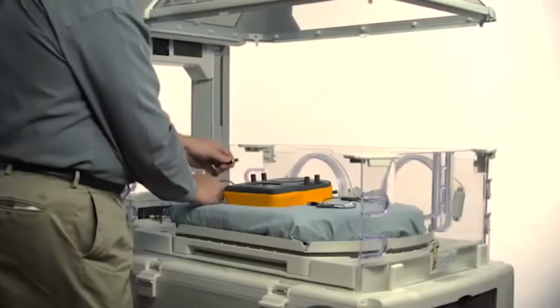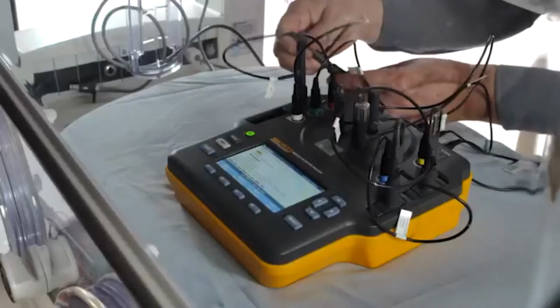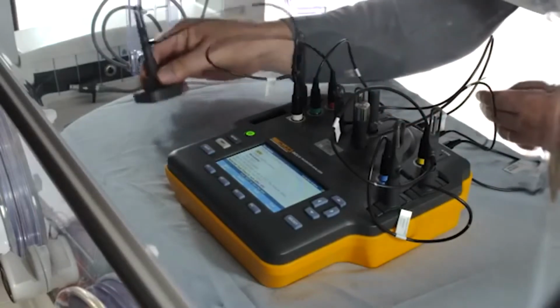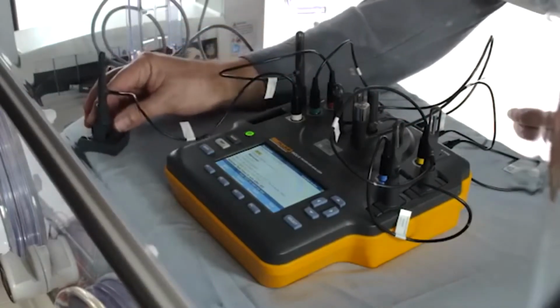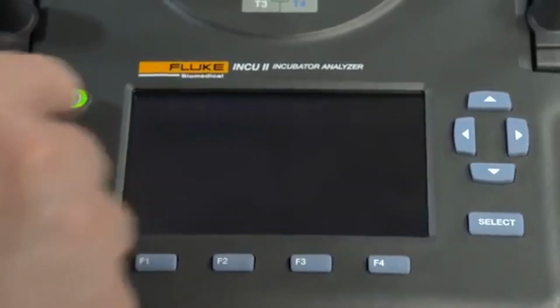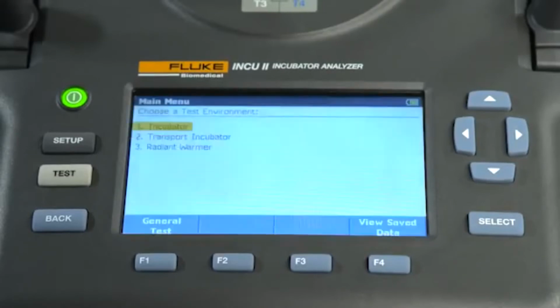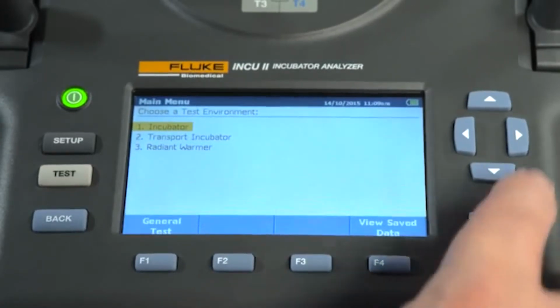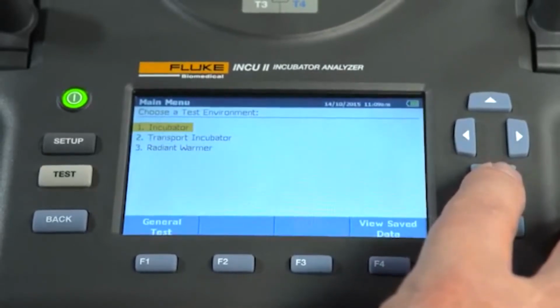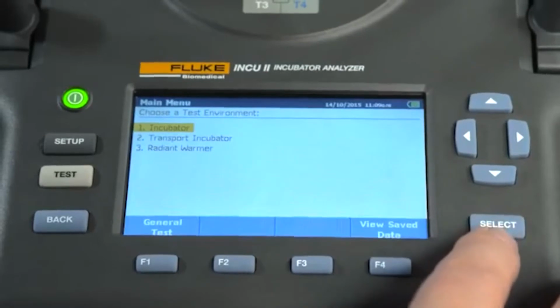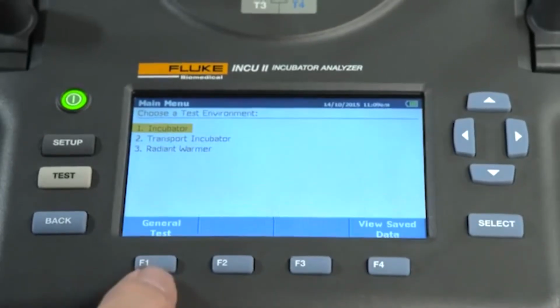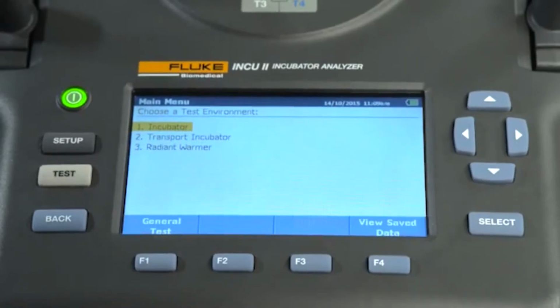To start, place the INCU2 in the incubator or radiant warmer you're testing. In this scenario, we're going to test an incubator. Remove and set up the temperature tripods and sensors. Position them in the middle of each quadrant of the mattress. When you first turn on the INCU2, it will do a self-check. When it's ready to test, the main menu will appear. Select a test environment. Choose a general test or view saved tests. For example, if you're going to run an incubator test, highlight Incubator from the Test Environment option using the navigational arrow keys and then press Select. You can also choose the General Testing option, which allows the user to log data without testing to a specific standard. But in this example, we're going to test to a standard.